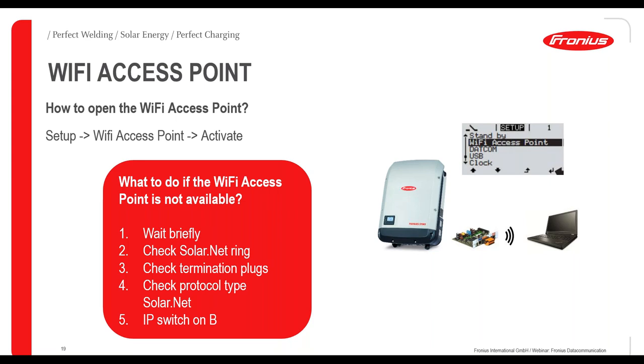If the Wi-Fi access point is not responding: first, wait briefly — especially on first installation, it takes a few minutes after switching on AC for the access point to become available. Second, check the SolarNet ring — verify termination plugs and communication cable are correct. Also check the protocol type of SolarNet. Importantly, check the IP switch (DIP switch) on the data manager — there is position A and position B, and it must be set to position B for the Wi-Fi access point to be available.